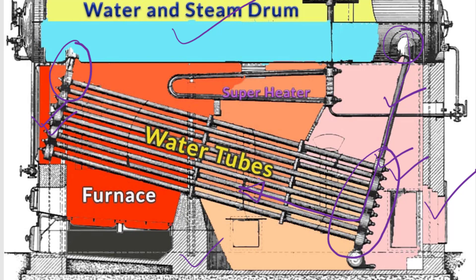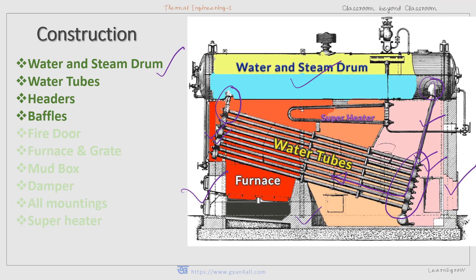The uptake header is present at the front end of the furnace and is attached to the bottom of the drum. It transmits the steam from water tubes to the drum. The steam produced goes up to the drum through these short tubes, and this is called the riser.